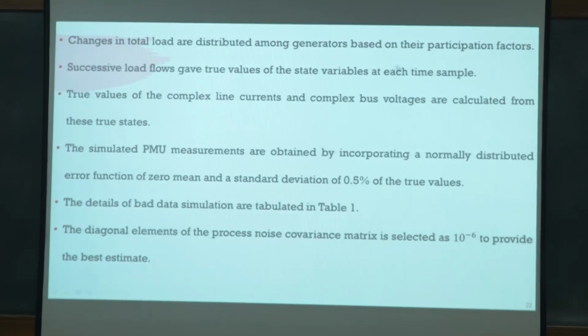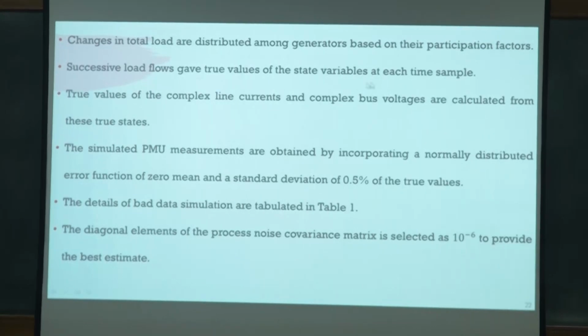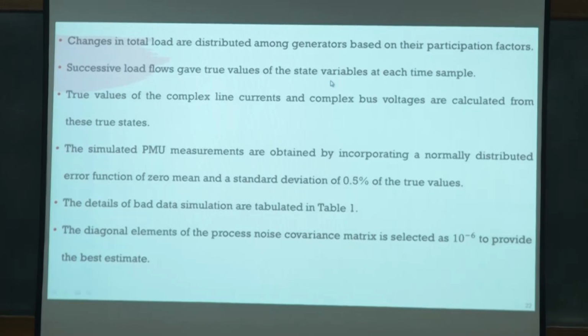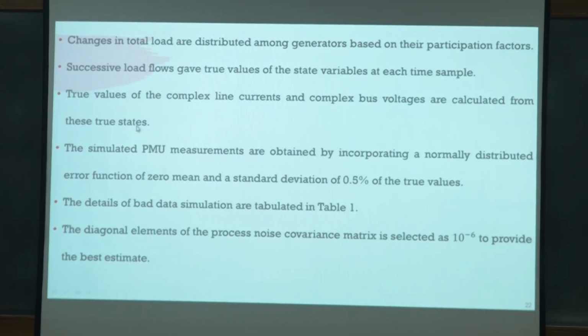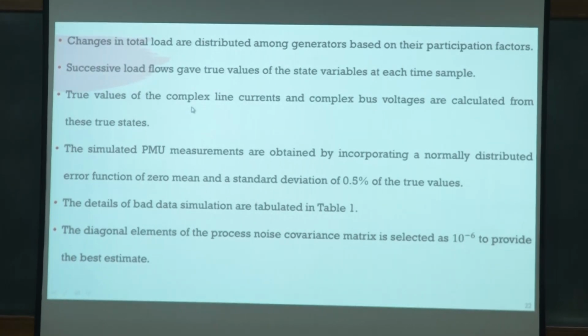Once system information is known to us, and loads and generations are also known to us, then we go for load flow studies to find out the state variables at each time step. Load flow studies at each time step give us the true states, true values, because whatever result we get from load flow is true values. Now we simulate using these true state vectors obtained from the load flow to calculate the PMU measurements. Voltage measurements are already directly obtained from the load flow solutions, and line currents we calculate using these values of the load flow.